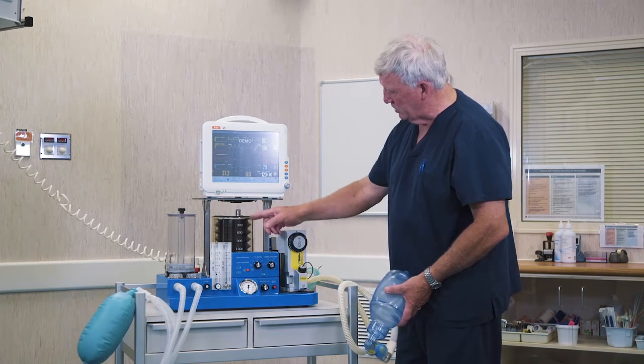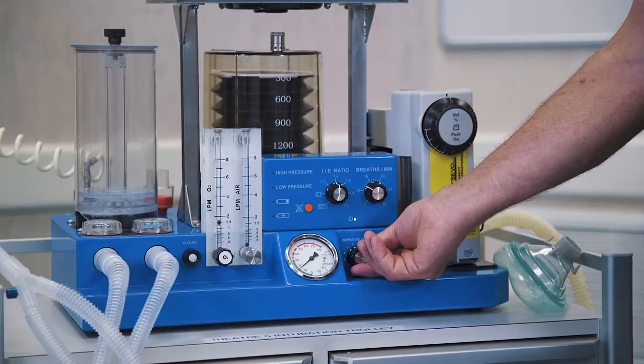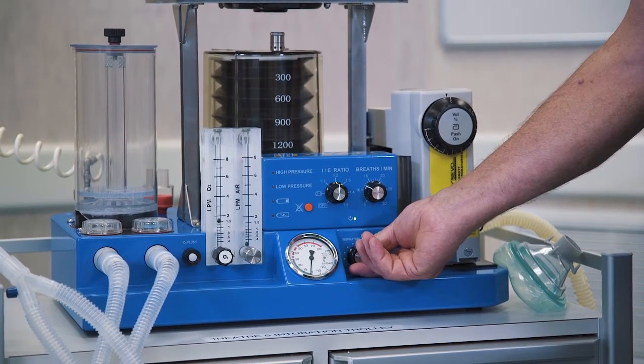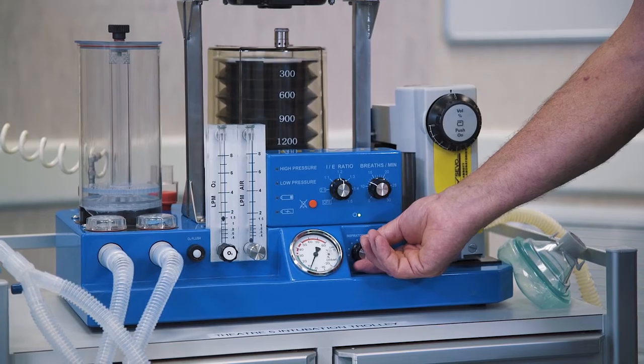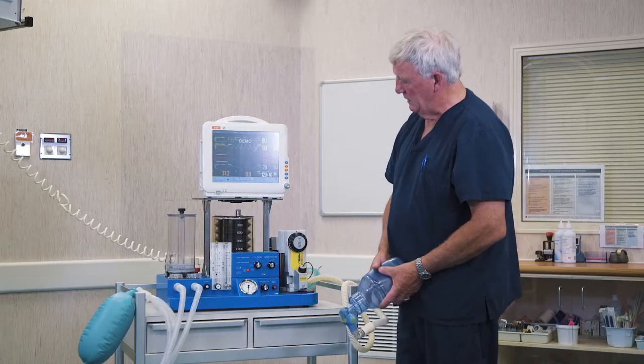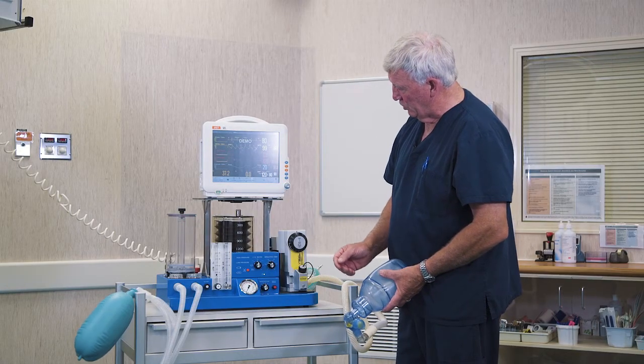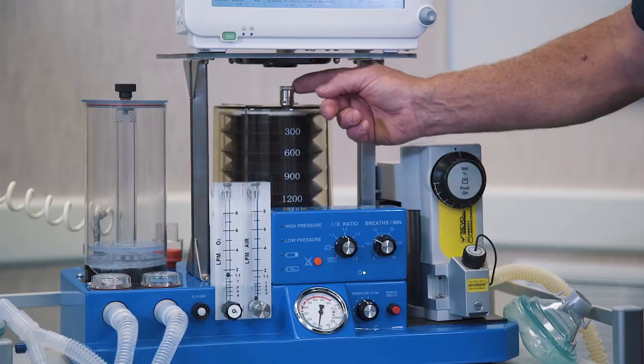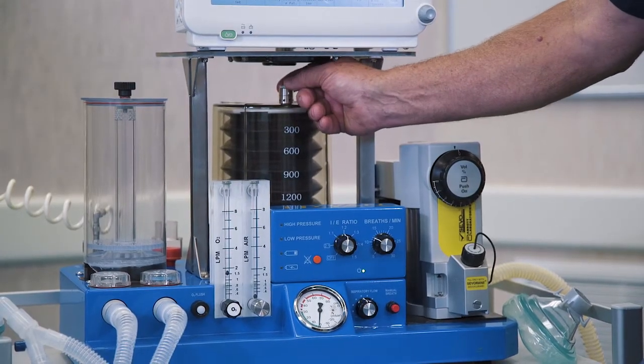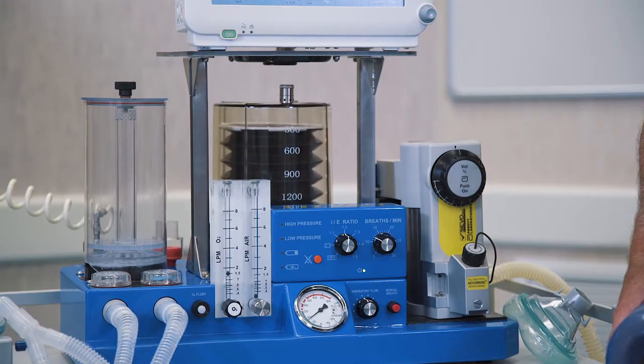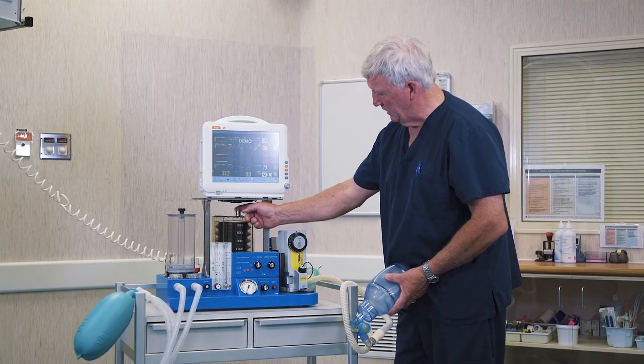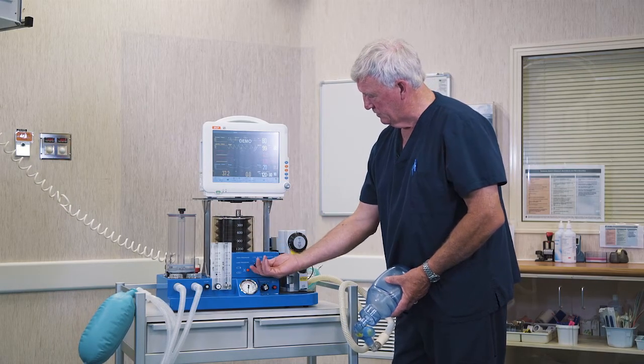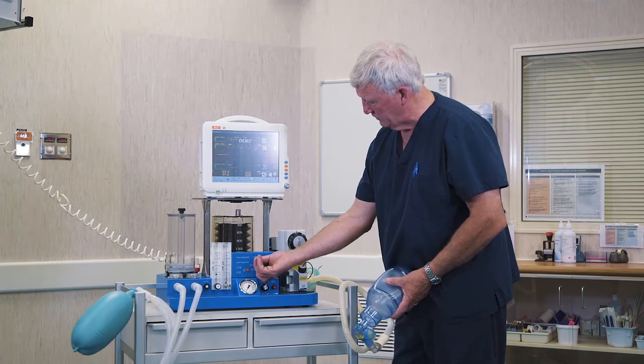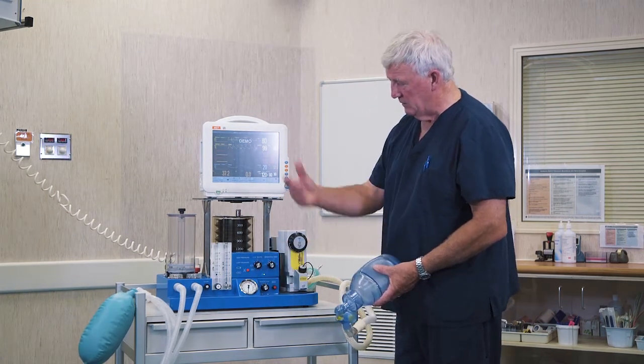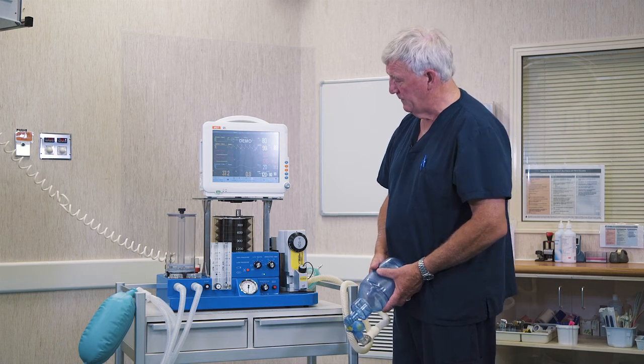Now, we adjust the tidal volume simply by adjusting the inspiratory flow. So if we want a tidal volume of, say, 500, I just increase the flow, and there it is, 500. If we want to use the pressure control mode, we can do that quite easily with this simple pressure valve in the back, and we can control whatever pressure we want to limit it to. So it's quite simple, really. And at the end of the operation, when you want the patient to start breathing in, we just turn the ventilator off, one switch, and let the patient breathe spontaneously.